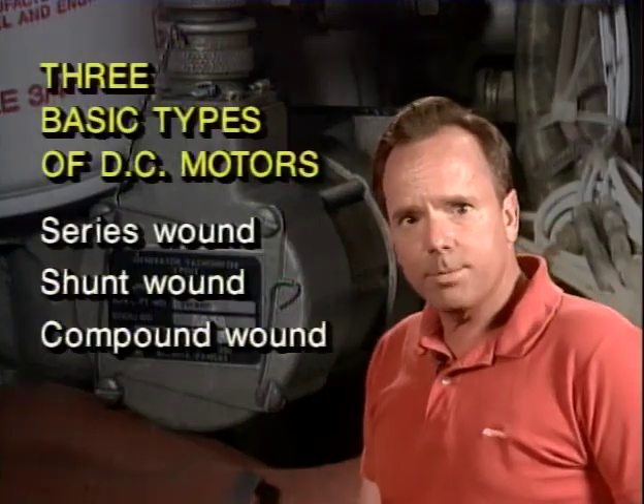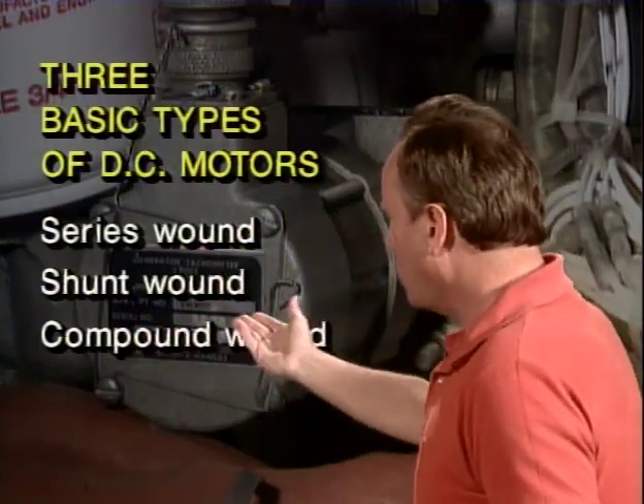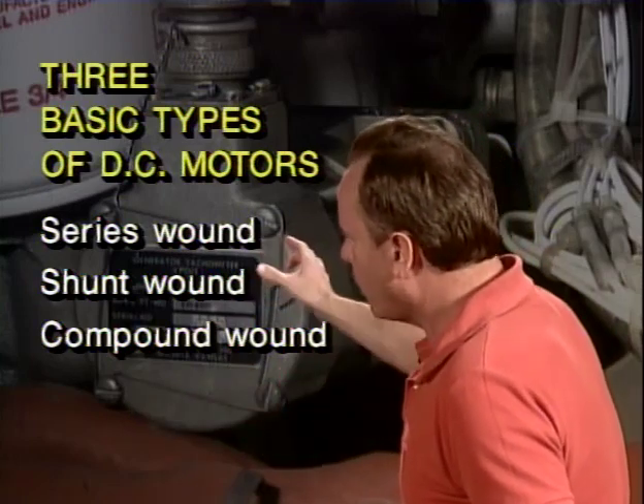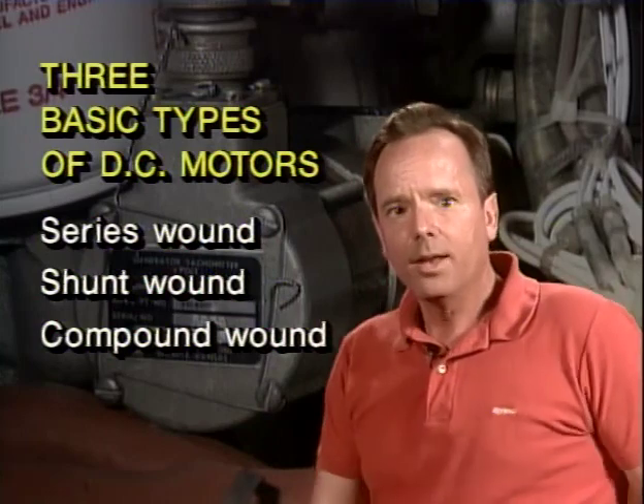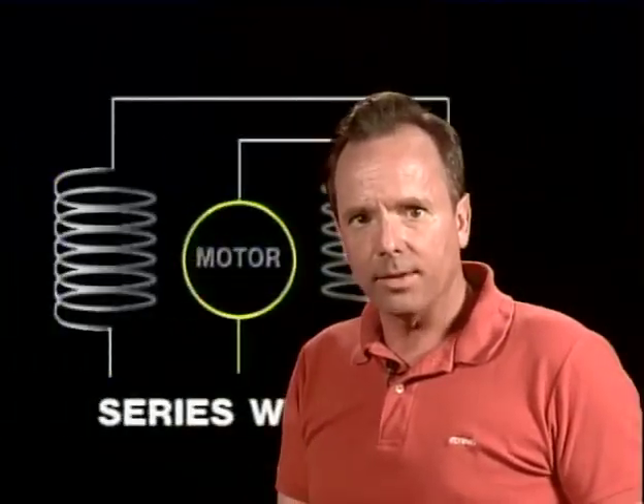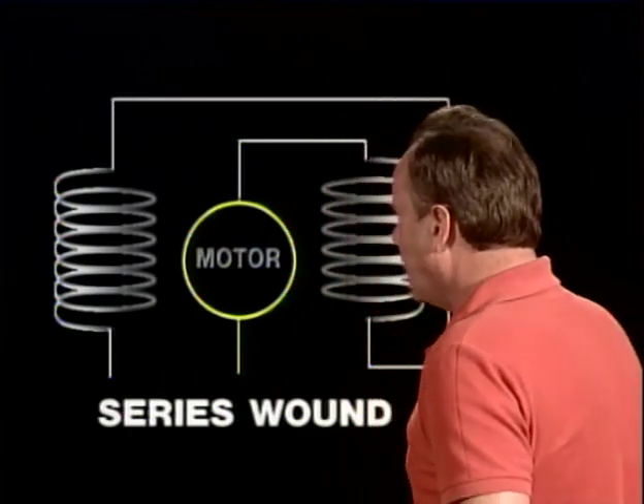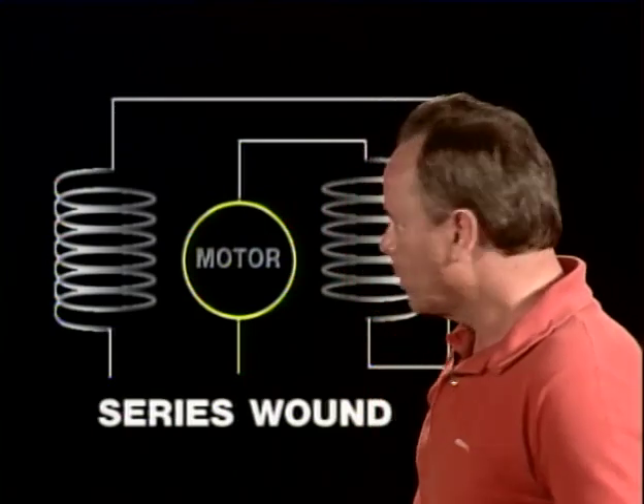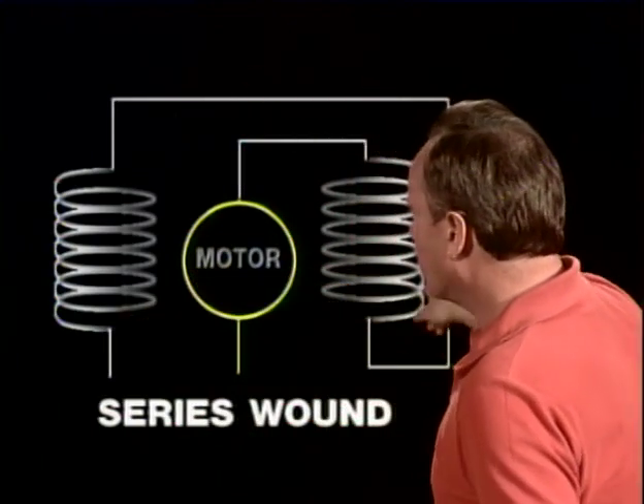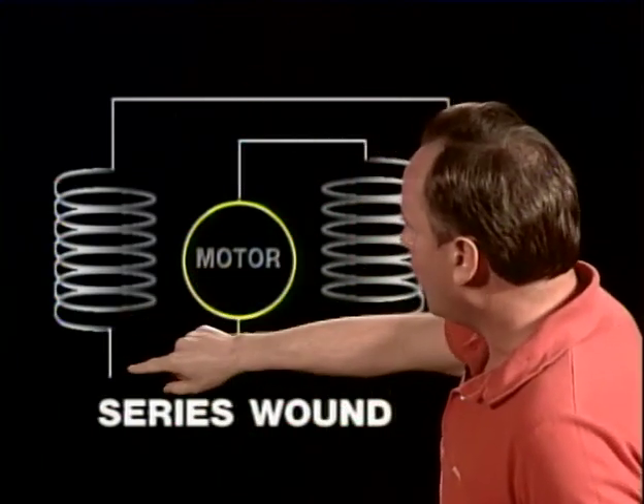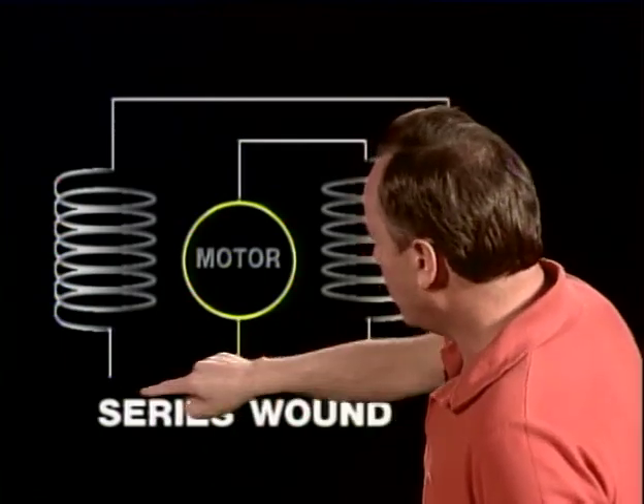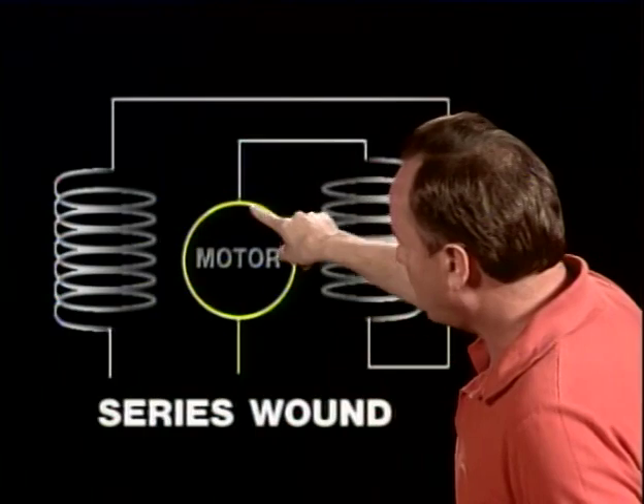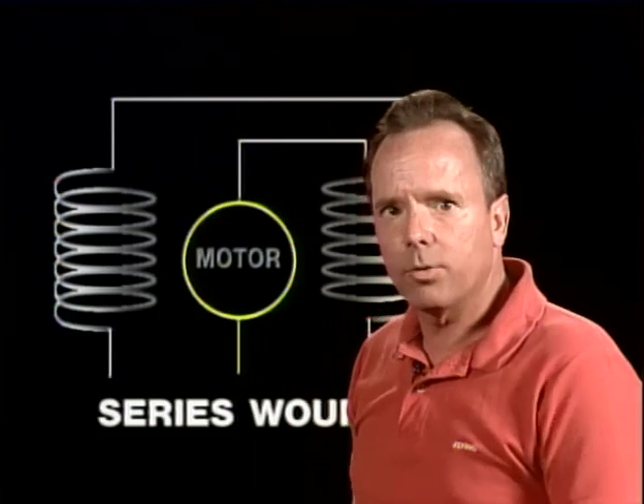All right, now let's take a look at some motor designs. There are three basic types of DC motors: series wound, shunt wound, and compound wound, which means it's both series wound and shunt wound at the same time. Now let's take a look at what they're talking about when they say this. We're talking about how a motor is designed and whether it's series wound or shunt wound. We're talking about how the electricity flows through the motor to the armature. If it's series wound, all of the electricity that goes through this motor goes first through the field and then to the armature. In other words, the field and armature are in series with each other, and that changes the characteristics of the motor.